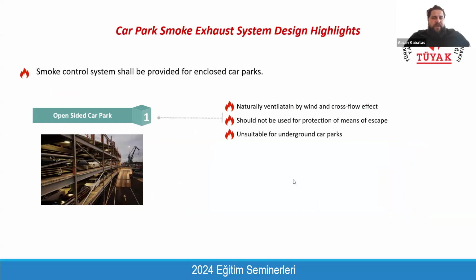And when you are designing a car park, you will need an exhaust system as well. Only for open car parks, as you can see from the figure, is a smoke extraction system not required. But all of the enclosed car parks should be equipped with a smoke extraction system, which also requires additional smoke exhaust and makeup air shafts. What is an open car park? It is naturally ventilated. That's why a smoke extraction system is not required.